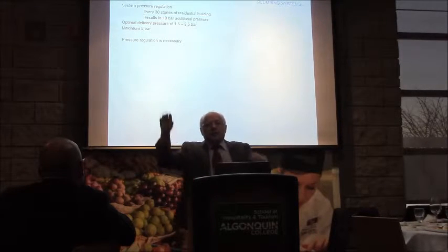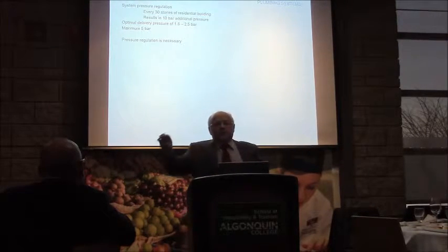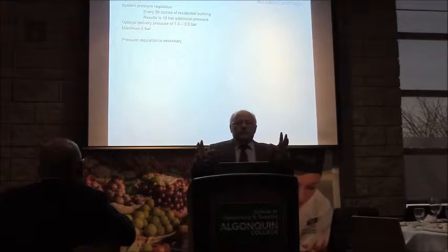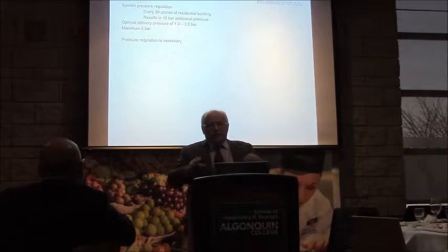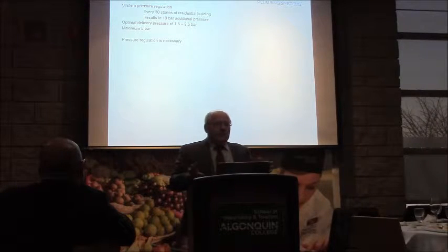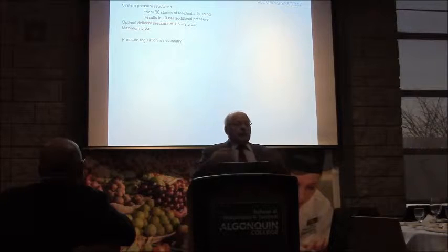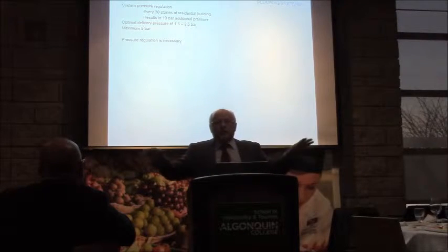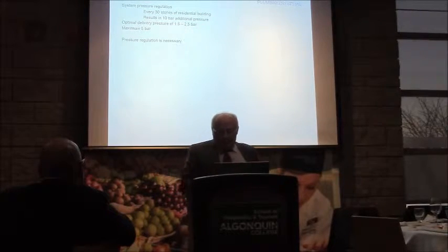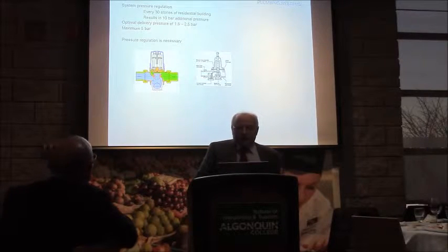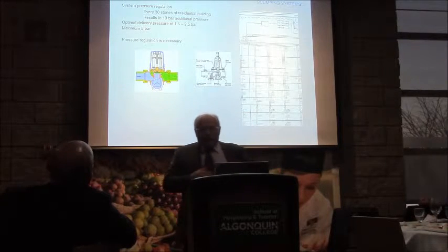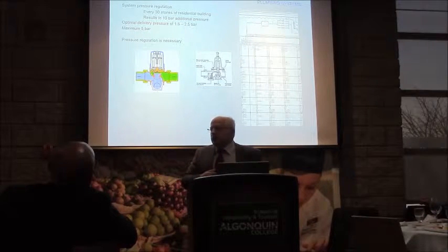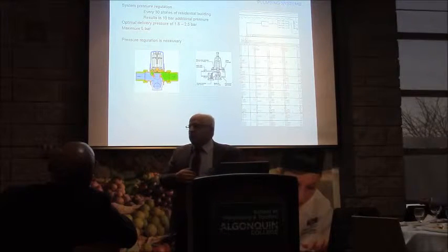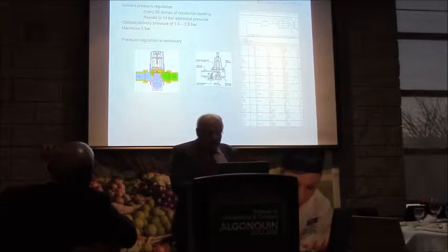I showed a little thing about keeping these zones separate. If you have the luxury of mechanical space above and below these zones, you can do great things by changing the loop and doing pressure reduction in spaces where you don't have to do a lot of it - you do it in one spot and do lateral distribution. It doesn't always work that way though. In the Shangri-La Hotel, they didn't want to see mechanical rooms halfway through, and I don't blame them, so we had to have pressure reduction.